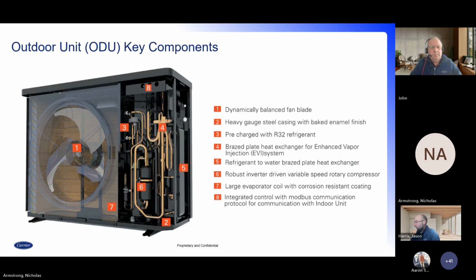Okay, slide. So what makes up the outdoor unit, of course, is a dynamically balanced fan blade. It's got a nice baked enamel finish, jacketing. It's a pre-charged R32 refrigerant, so that's important to keep in mind. It's not something you have to charge up at the time of installation. It's already done for you. Monoblock design. It has a robust inverter-driven variable speed rotary compressor, and of course, it also has the large evaporator coils. It's corrosion resistant as well. Okay, slide.